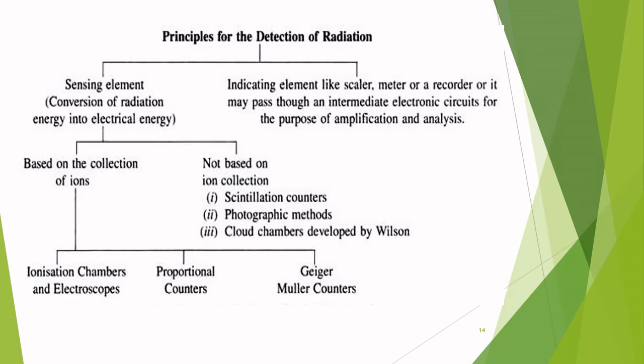Principles for the detection of radiation. The sensing element causes the conversion of radiation energy into electrical energy. The indicating element, like a scaler, meter or a recorder, may pass through intermediate electronic circuits for the purpose of amplification and analysis. Sensing elements based on the collection of ions can be of the following types: ionization chambers and electroscopes, proportional counters, and Geiger-Müller counters.